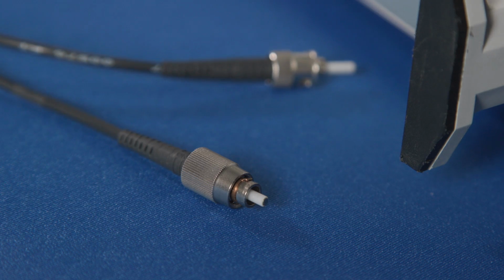The next thing that we'll be doing is connecting the laser probe to the laser card, but we wanted to highlight the laser channel on the probe has a raised copper nub, which is a keyway for the connection on the card, and it's critical to get this aligned properly.